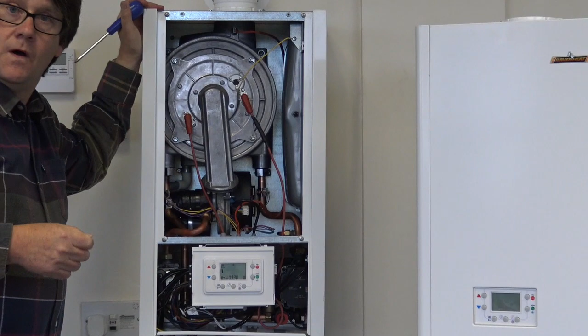Drop down, here we've got the flue sensor. To the right of the flue sensor we have the expansion vessel. As you can clearly see, guys, the Schrader valve is there slap bang in front of you. It's a dream, okay? So on your annual service, when you're checking the pressure in the vessel, it couldn't be any easier for you.